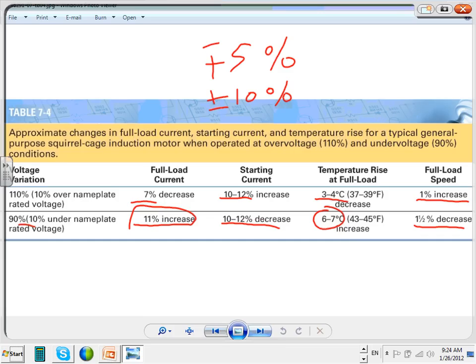So we go over this in detail, guys, with the electrician. You have to understand. You walk into a building and the motors are hotter than normal. Pay attention to the voltage that's coming to you from the utility. It has to be within 5%, plus or minus. Otherwise, your equipment will act weird.